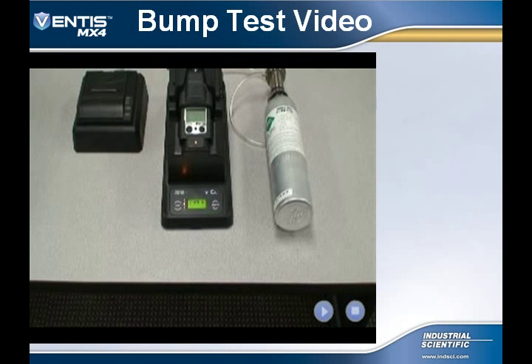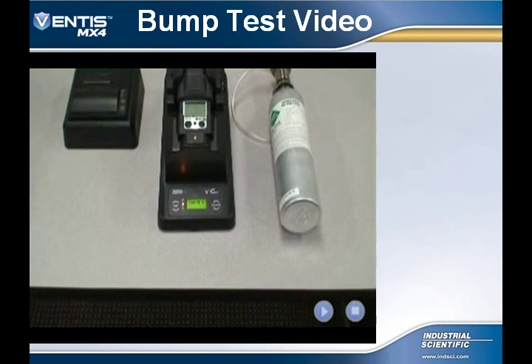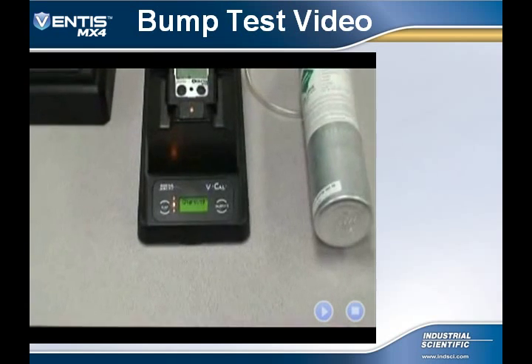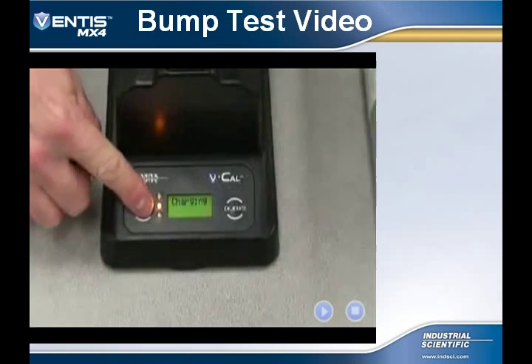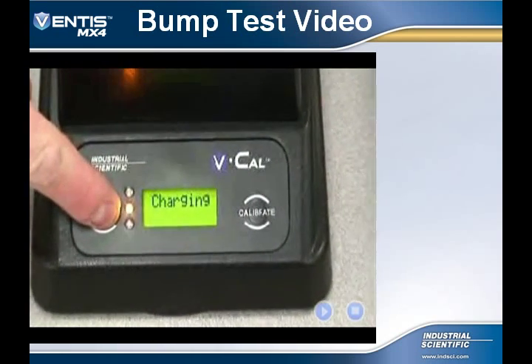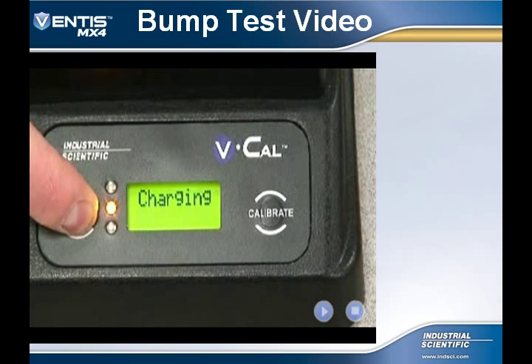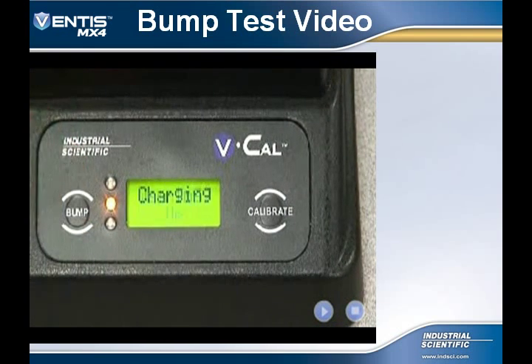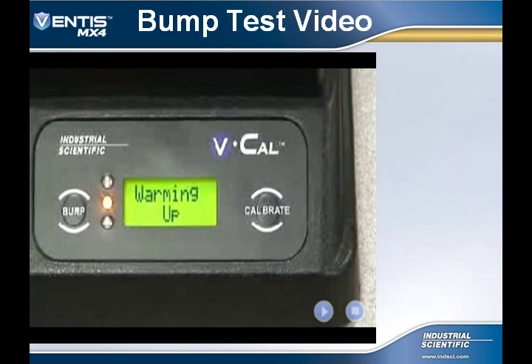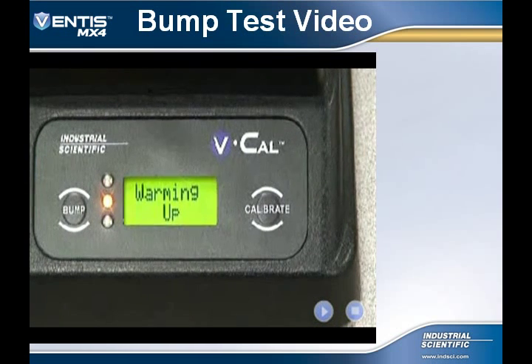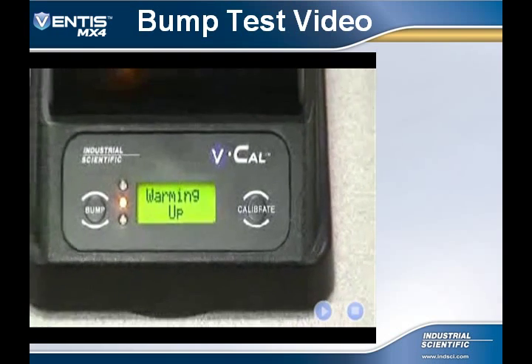This video will walk you through the bump test procedure of the VCal. With the Ventis MX4 inserted into the VCal, press and hold the bump button for approximately 3 seconds. The VCal will turn the instrument on and the display will toggle between warming up and Ventis MX4.